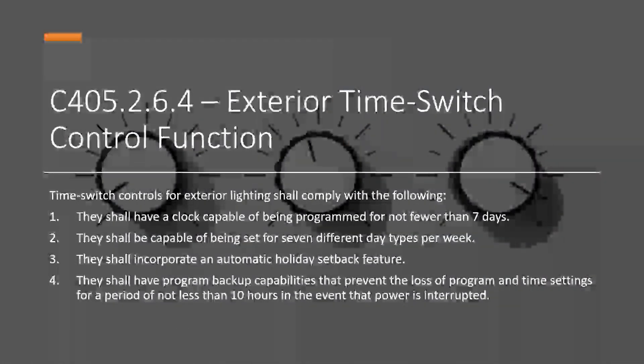Exterior time switch control functions shall comply with the following: have a clock set for not fewer than seven day types per week, incorporate an automatic holiday setback feature, and have program backup capabilities to preserve program and time settings for a period of not less than 10 hours.